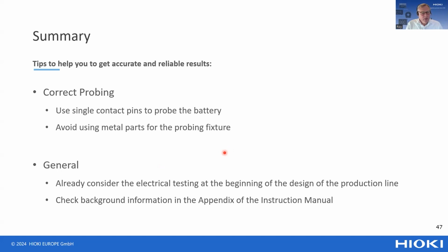For probing, always use single contact probes - this will give you much better repeatability of your measurement. And when you have a probing fixture, always try to avoid metal parts in it, because metal parts can also be a source of eddy current.